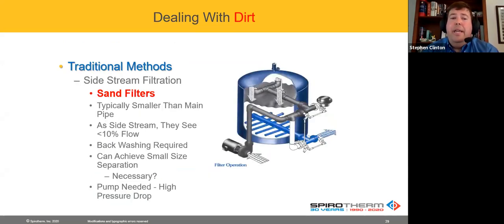The next type, again typically in a side stream, is a sand filter. Sometimes you see this more in condenser water systems or open systems, or maybe a chilled water system. People are trying to get down to really small particles, maybe a half a micron or a micron. Well, in our industry, what we typically find, looking at various materials and reference guides, is that the 10 to 75 microns is often where you have the most fouling of coils and heat exchangers. The American Drinking Water Foundation says that if you get down to around 5 microns or smaller, that's really stuff that a biocide can handle. We get down to 5 microns over time, as we'll tell you about in a second, in a closed system. Basically, sand filters work pretty well. They can polish pretty well, but oftentimes we see them 6 months to a year in turn into something like concrete, if not properly maintained.